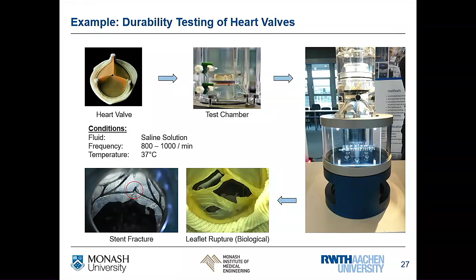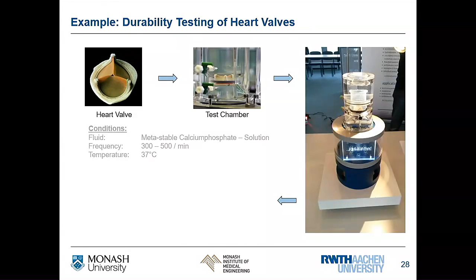You go with 800 to 1,000 cycles per minute instead of the 70 per minute that we have. So that is a test you can do, and then you can crimp them, uncrimp them, and test again, and see how much it affects the valve. The next thing: if you take not water or saline solution, but a solution that has a lot of calcium phosphate in it. Calcium phosphate is what causes the calcification. Particularly in young children, when they grow up they have to grow bones, and that means they have a lot of calcium phosphate in their body, so you may never put a biological valve into them because they calcify immediately, also as a little comment.